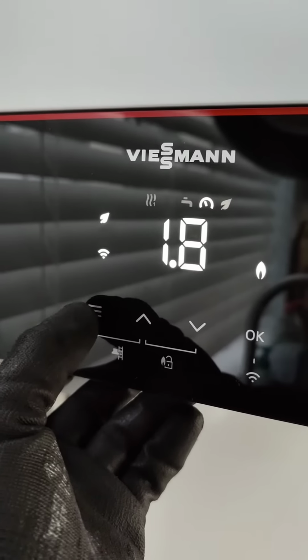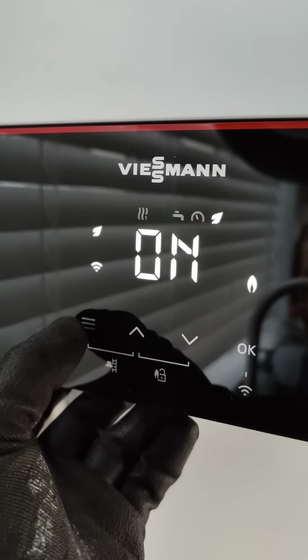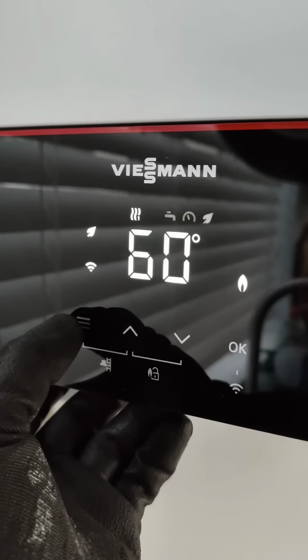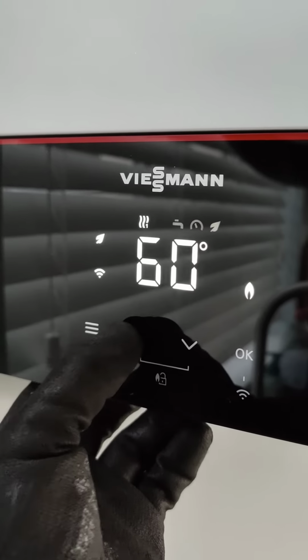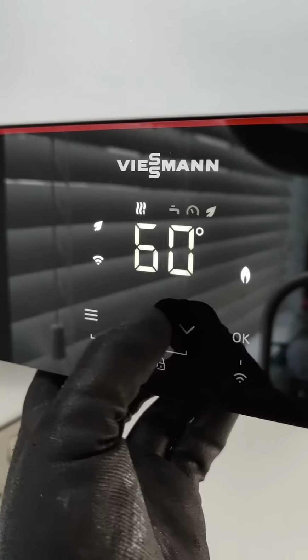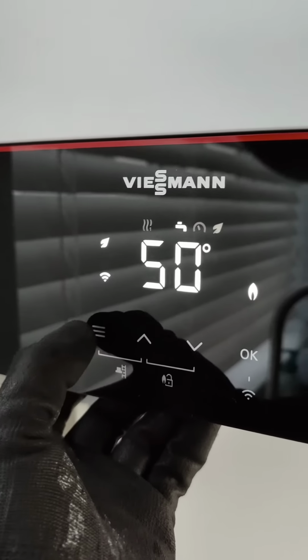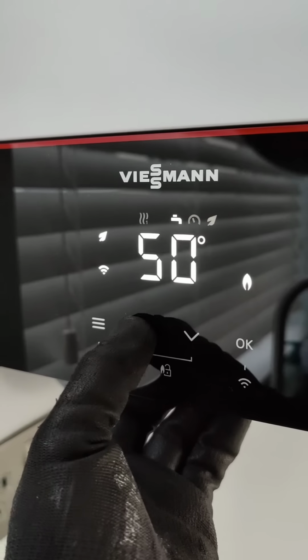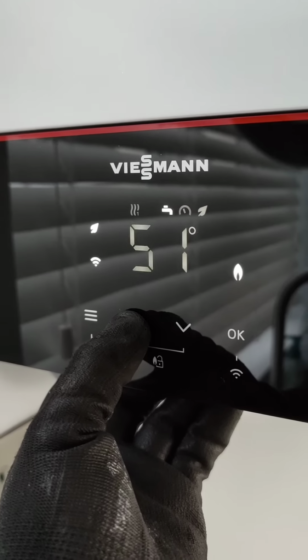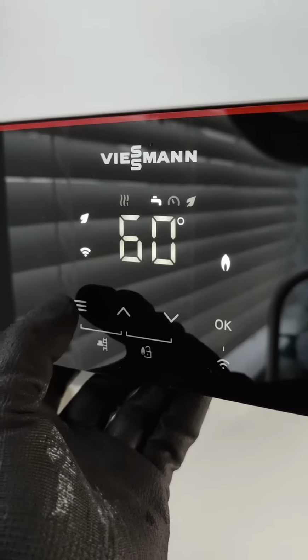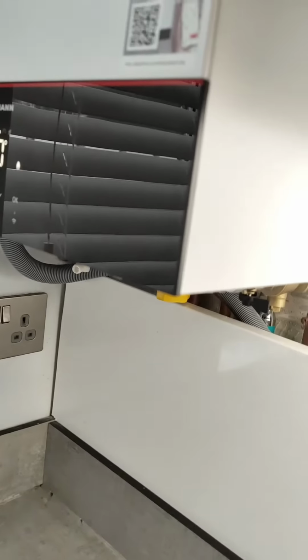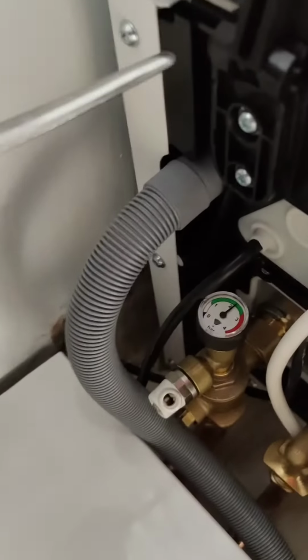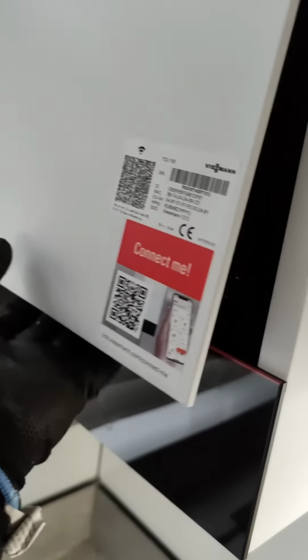Just by pressing the menu button we can cycle through whether we want eco for the hot water on and off. We can set the flow temperature. We can also set the hot water temperature up to a maximum of 60. Underneath here, two little holes. We can just jab something up each side. Get the cover off.